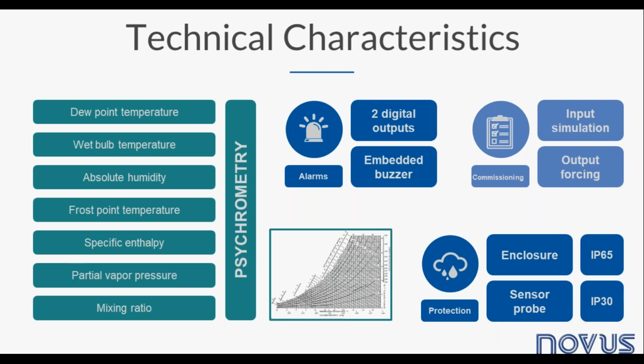An innovative feature for commissioning or diagnosis is the ability to simulate output signals or to force an output signal. The technician may simulate all conditions in the integration stage of commissioning with the PLC or controller system. The device is constantly calculating all those 7 psychrometric properties from the measured relative humidity and temperature. Any of those properties can be displayed, transmitted to analog output, or read on the Modbus table.